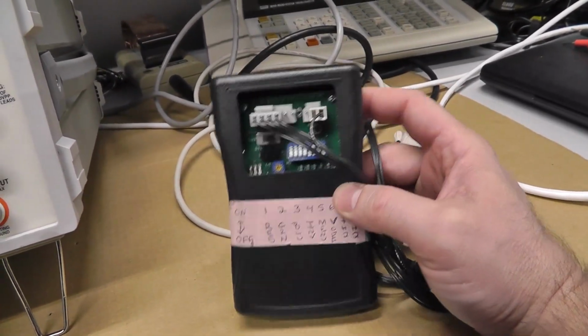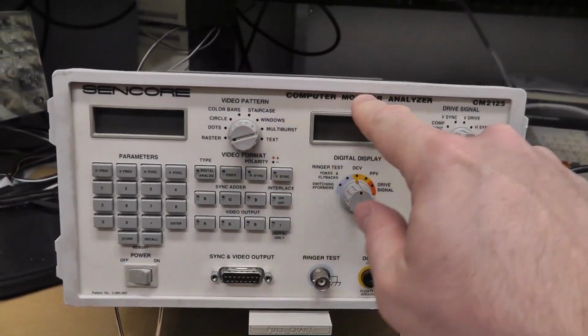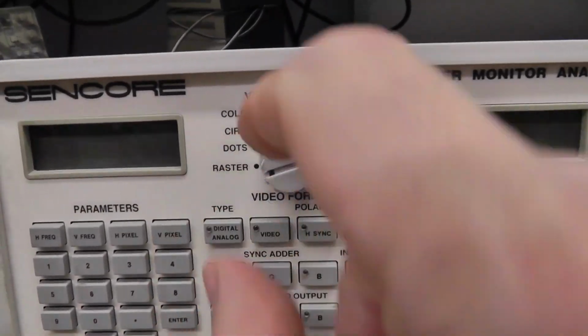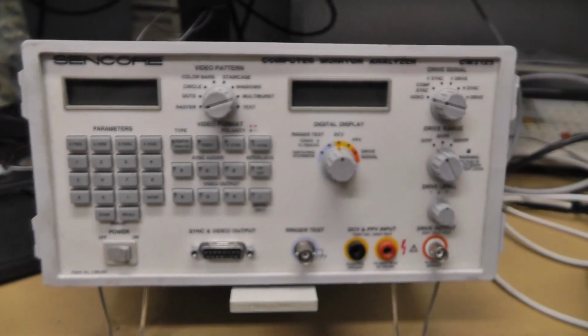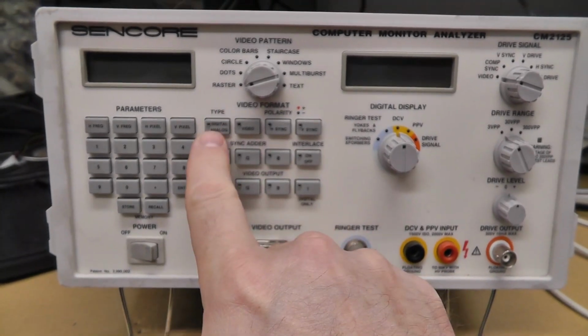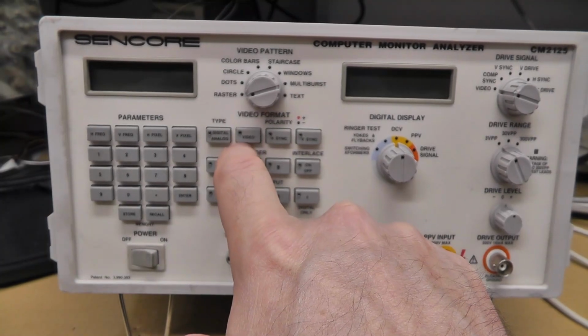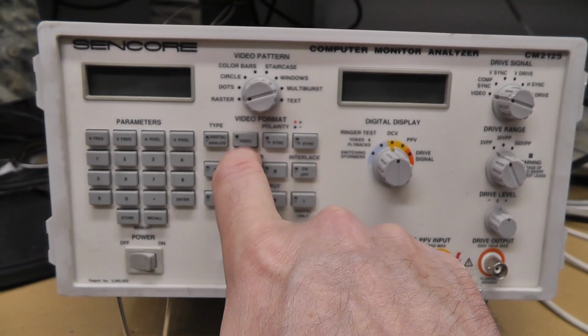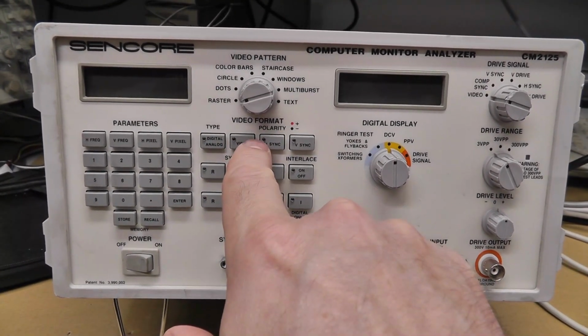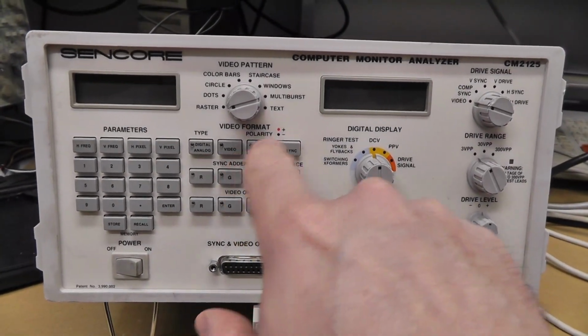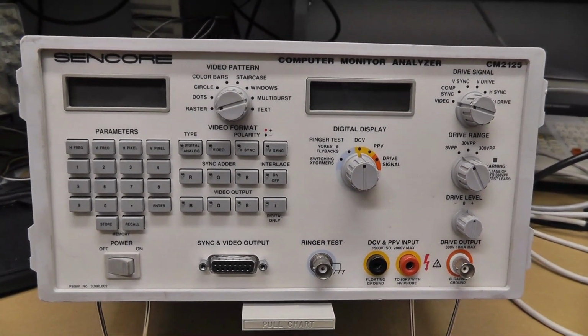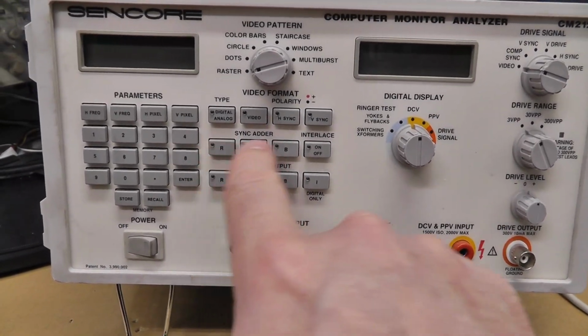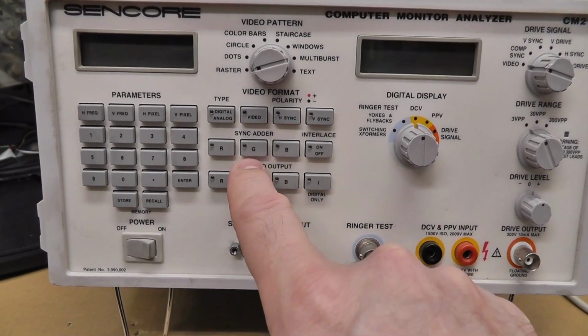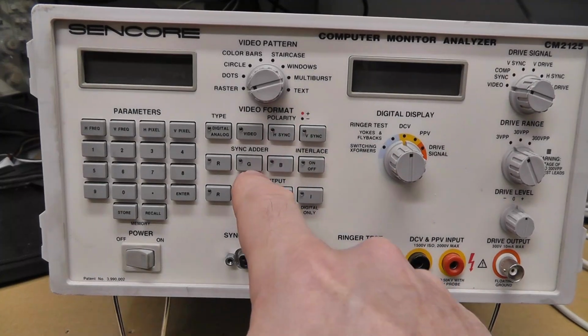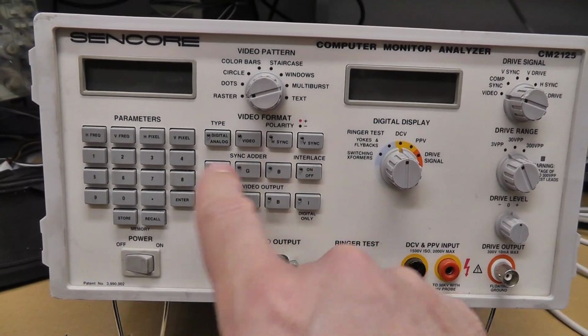But the TPG works fine, and it puts out different test patterns. So this does the same thing. Computer monitor analyzer. You have different test patterns that you can put out: raster, dot, circle, color bars, staircase, multiburst, text. It's really for testing computer monitors, not arcade monitors. Some of the features you can do is inverted video, so instead of the video blanking signal being 0, the blanking signal is 1 and the video signal is 0, or that's reversed. You can have negative or positive horizontal and vertical sync, as well as composite sync. You can actually have sync over the different color lines. Like I think on Apple computers, some monitors might have sync over the green video line, and you can do that.